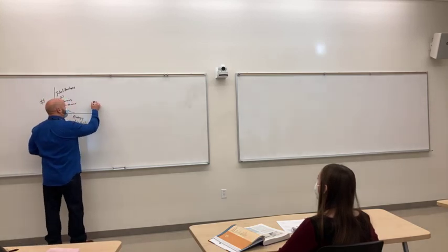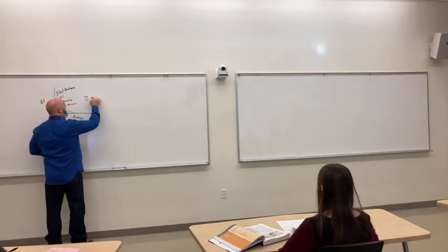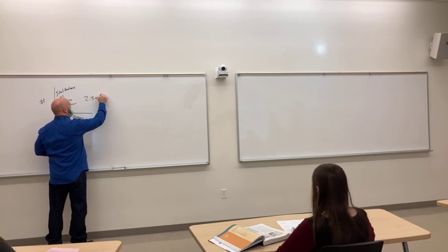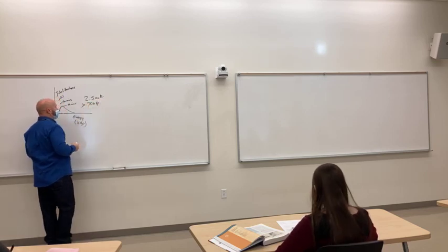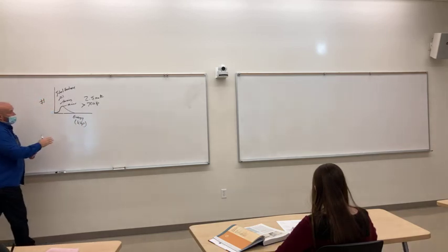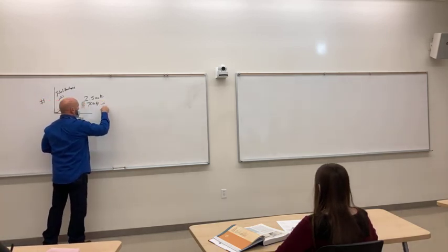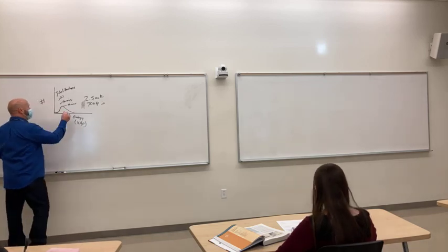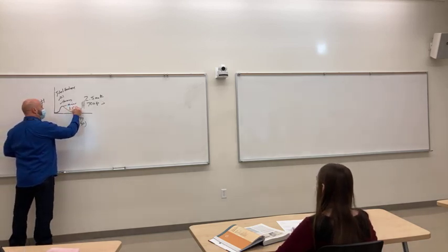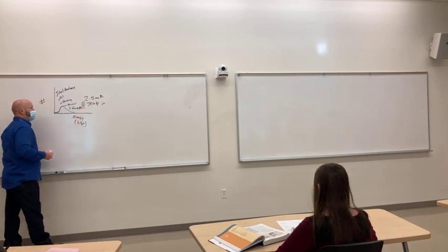So in a diagnostic X-ray tube, you have to have 2.5 millimeters of aluminum equivalent if you're operating above 70 kVp. Okay? So, 70 kVp or above. All right? So all of your diagnostic tubes are going to be set up with that. If all this only gets us to 1.5 millimeters of aluminum, then what do we need?